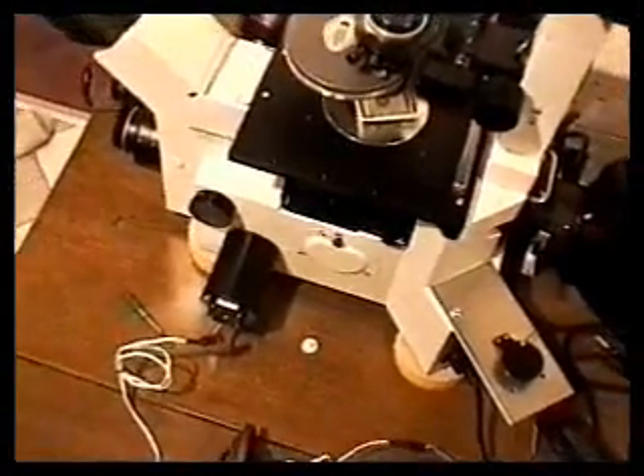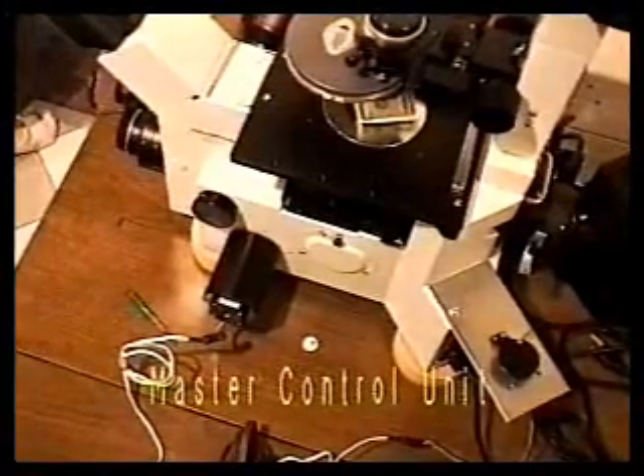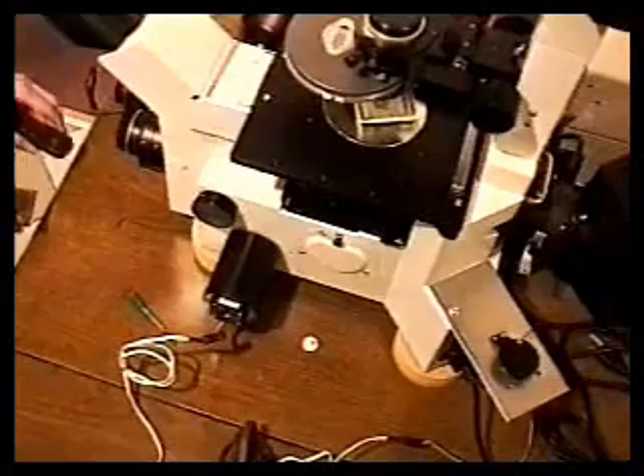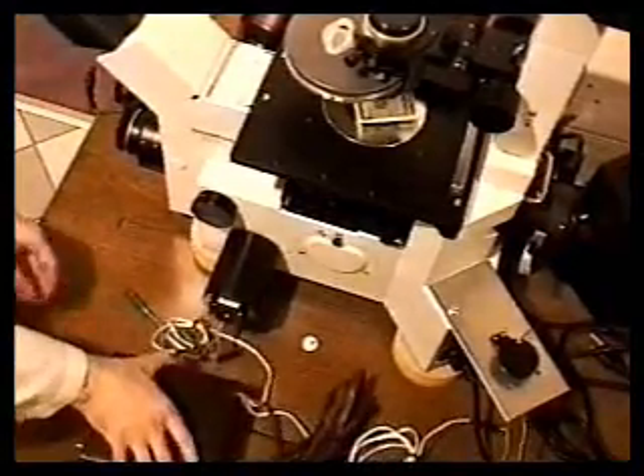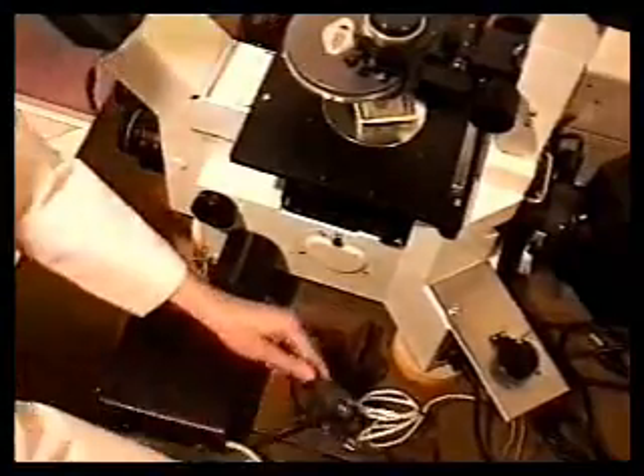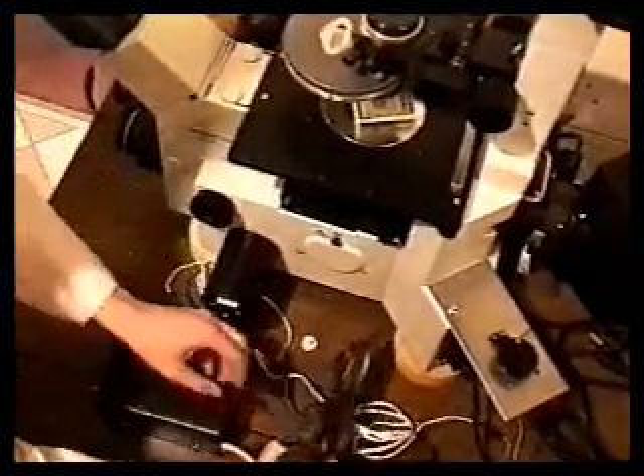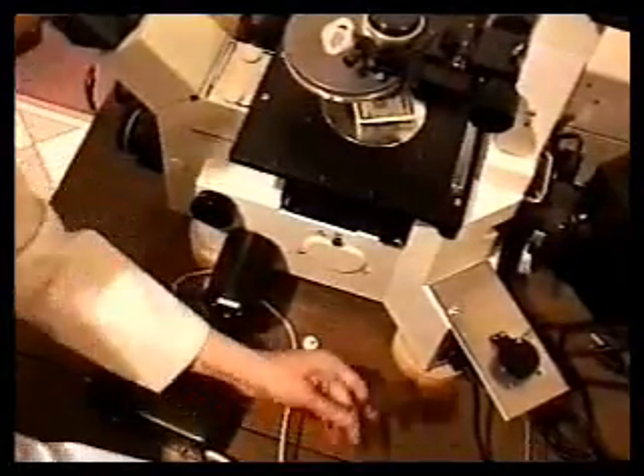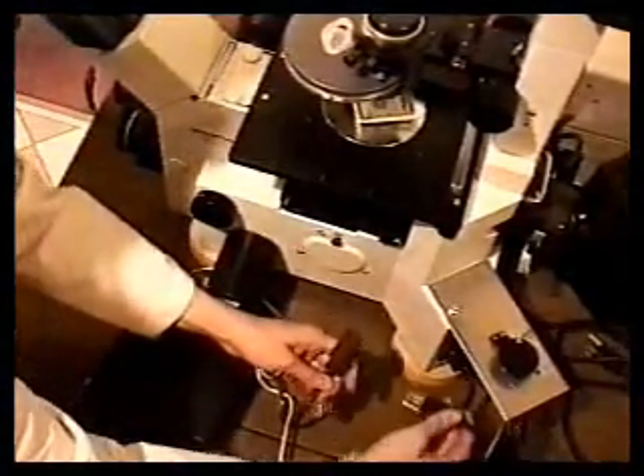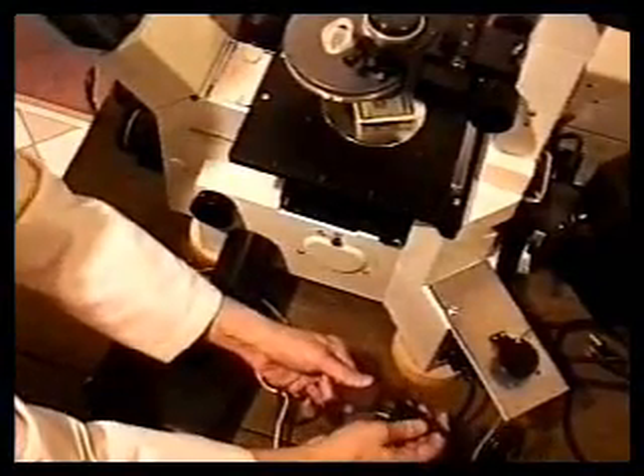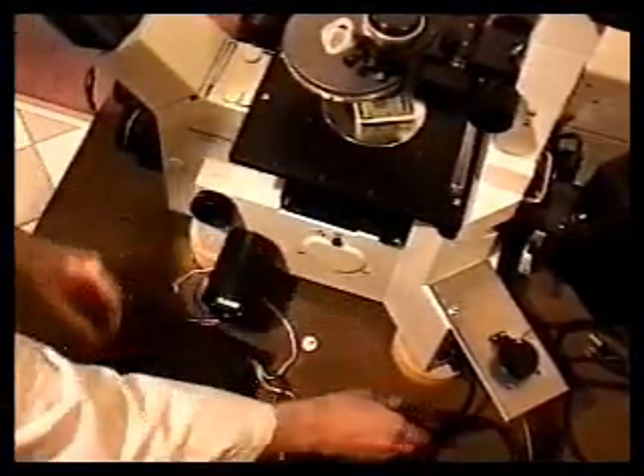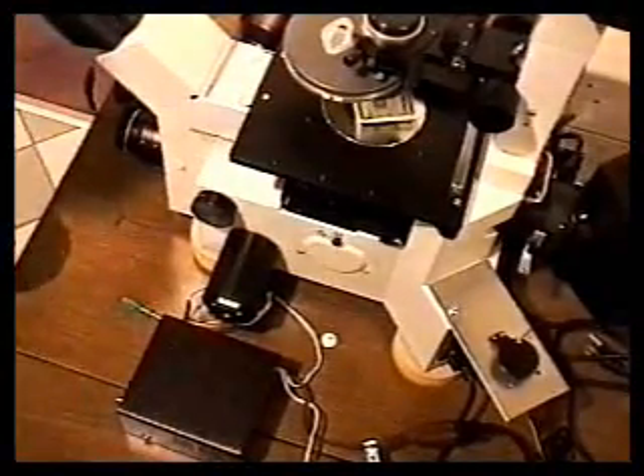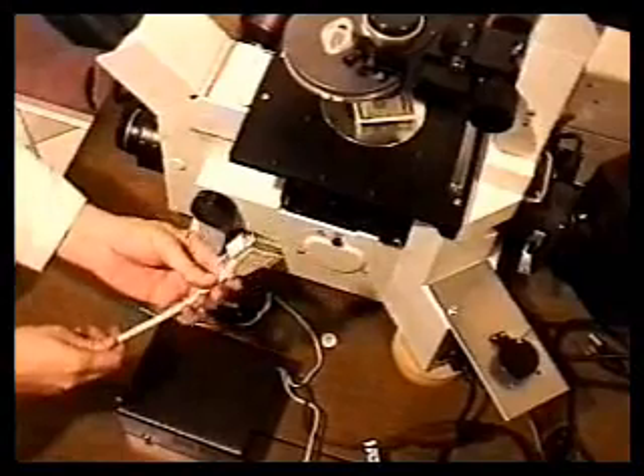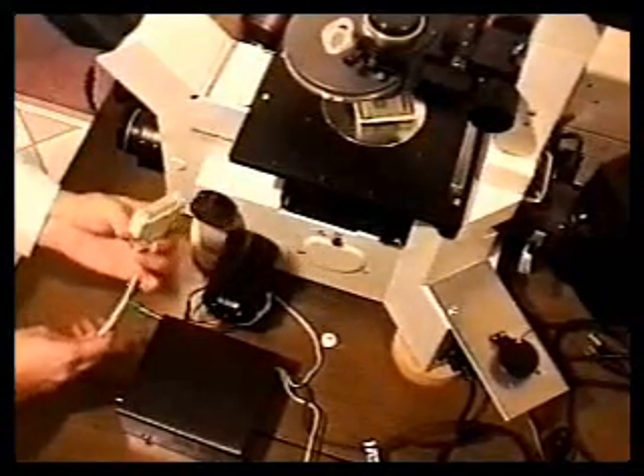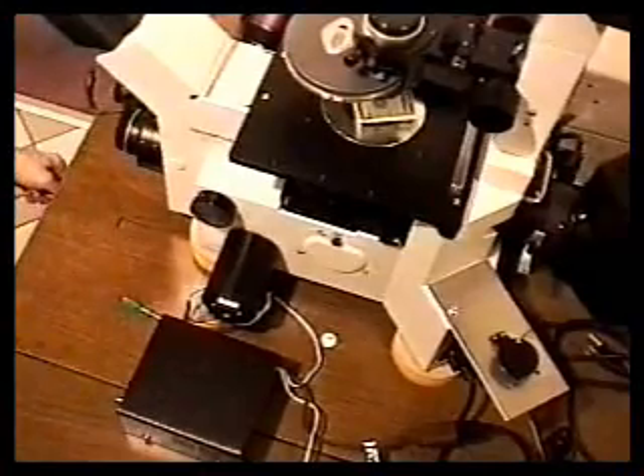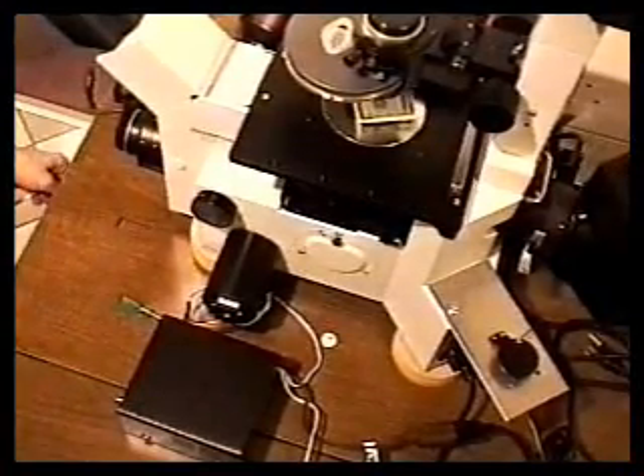Now all that's left are the main power connections for the master control unit. So here's the master control unit right here. Its power plug gets plugged into an electrical outlet like this, and it has a 3-prong receptacle. You use this to plug in the power cord that comes from the microscope's lamp power supply so that the control unit can control that. And then there's a parallel port connector, and that plugs into the parallel port on any PC compatible computer. And you're all set and ready to go.